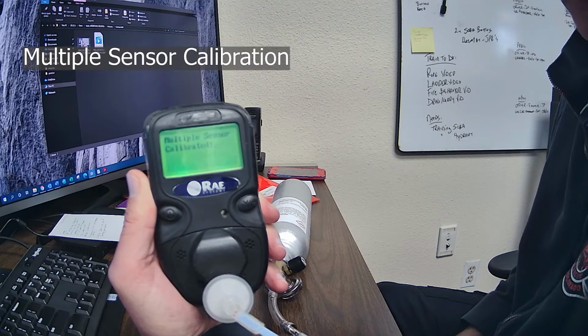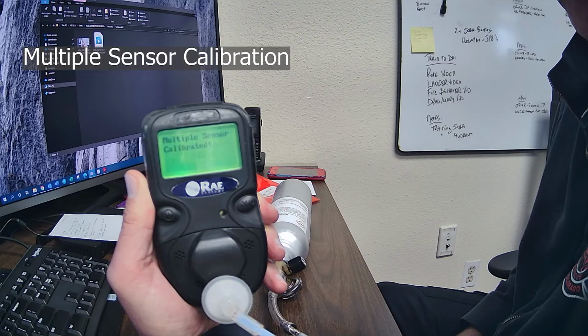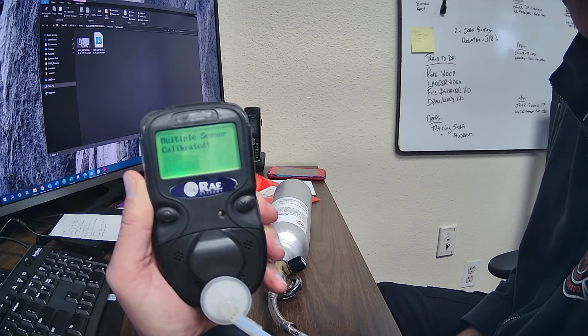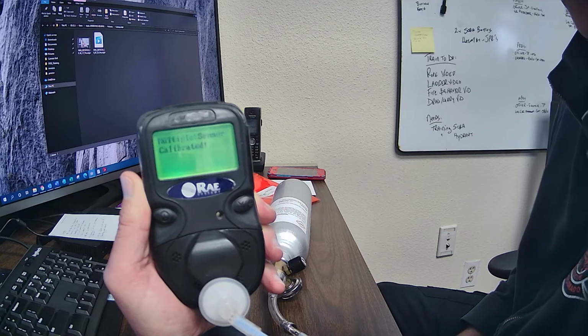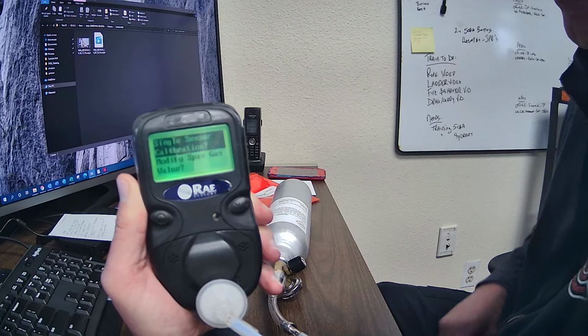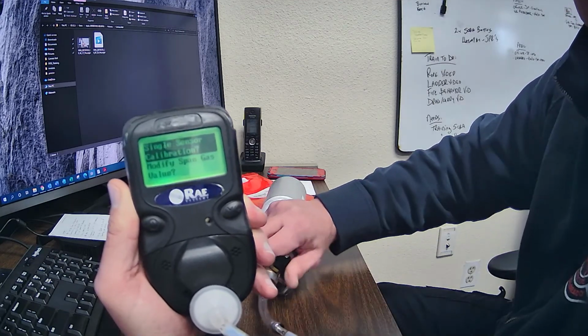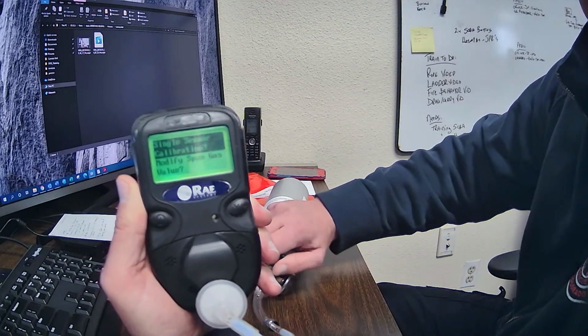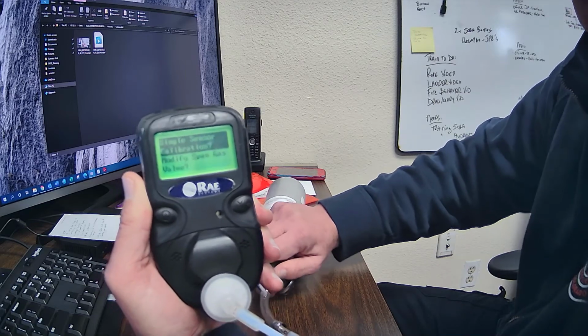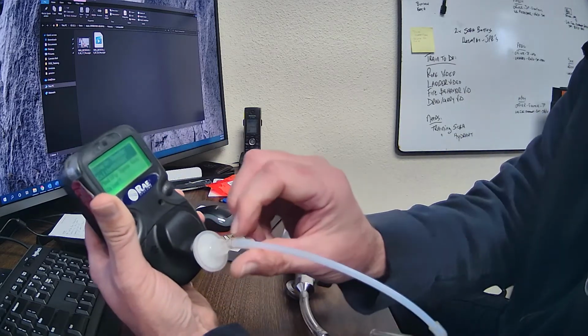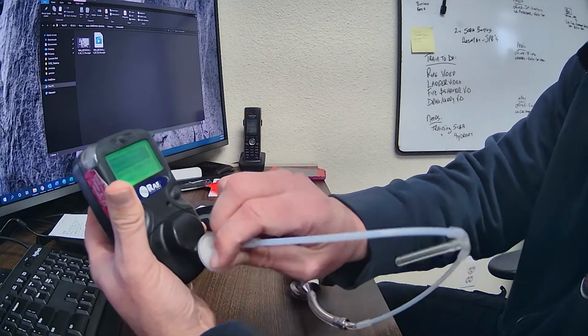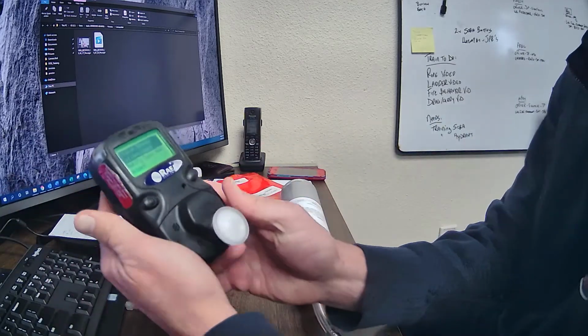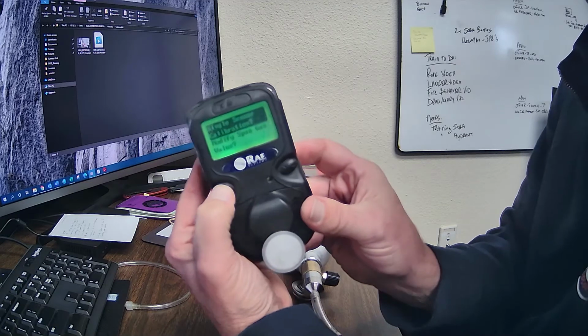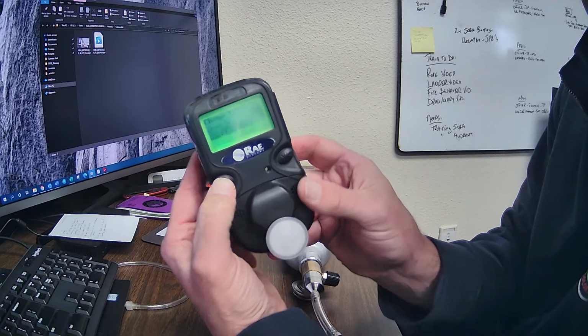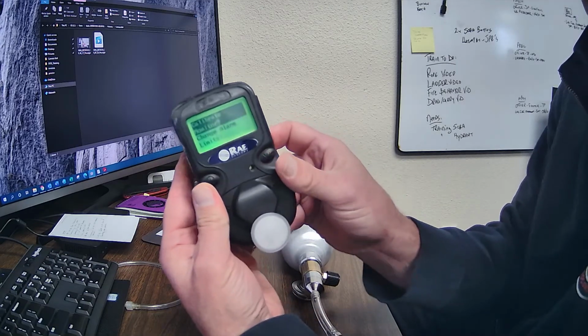All right, so it's complete, multi-sensor calibration, and it says calibrated with an exclamation point. Awesome. Do we have any alarms? I'm not hearing any. I'm not seeing any. So we can go ahead and turn off our gas because it's starting to smell. We can go ahead and disconnect our tube from the filter. And then, if it's not alarming, we're good. You just calibrated the 4-gas.